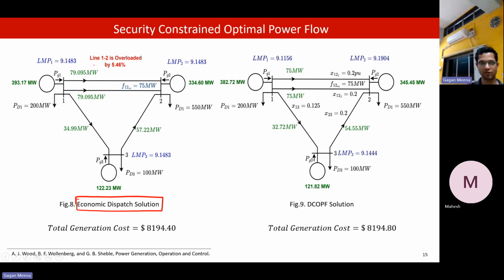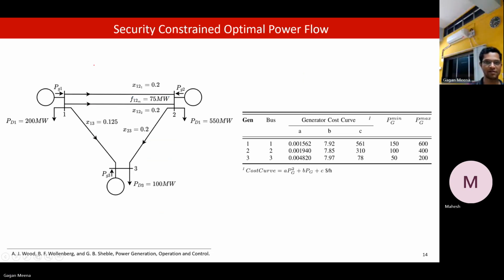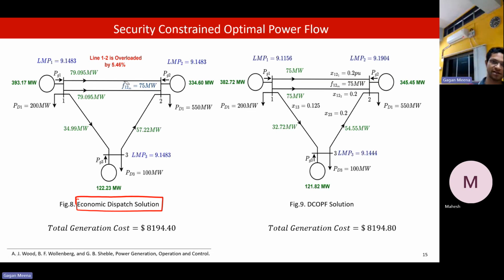here we have 2 lines. Here you see there is a redundancy between bus 1 and bus 2. We have 2 lines, each of them with a capacity of 75 megawatts. And these other 2 lines have very high capacity. Only this line has a capacity of 75 megawatts.